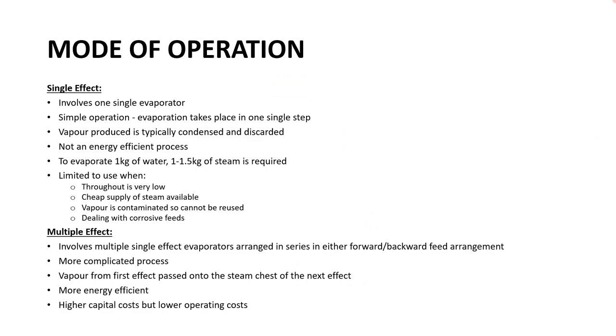As a result, single effect evaporators are normally only used when the throughput is low, there is a cheap supply of steam available, when the vapour is contaminated such that it can't be reused, or when dealing with corrosive feeds where a specially designed evaporator constructed from expensive material is required.